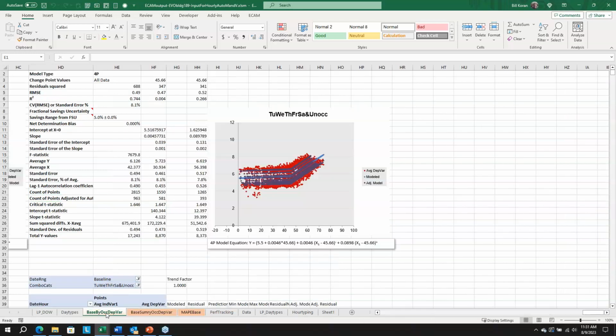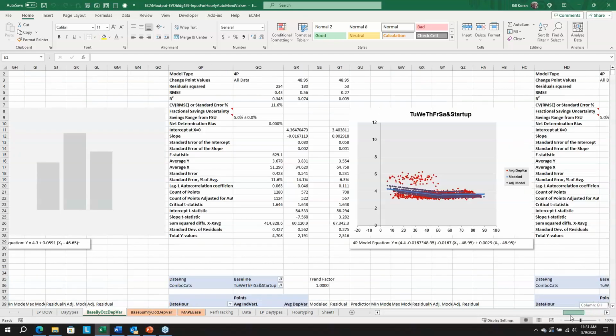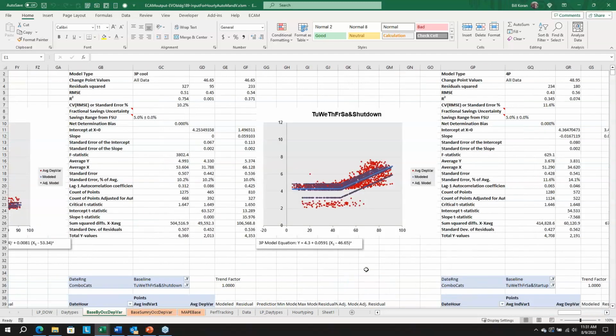So let's look here at the individual models. Here's the last one that was created. We have day types of Tuesday, Wednesday, Thursday, Friday, Saturday lumped together for the unoccupied period. We can go to the left and see a model for the startup for those days, the shutdown for those days, etc. You might see different clouds of data, and that's because we've grouped into 4 time periods during the day. There could be an hour within one of the four periods that doesn't really match the other hours, or there could be a gradual increase in energy use during startup, for example. So the energy use each hour is going to be slightly different, which is also accounted for, and that's why we see multiple fit lines here.